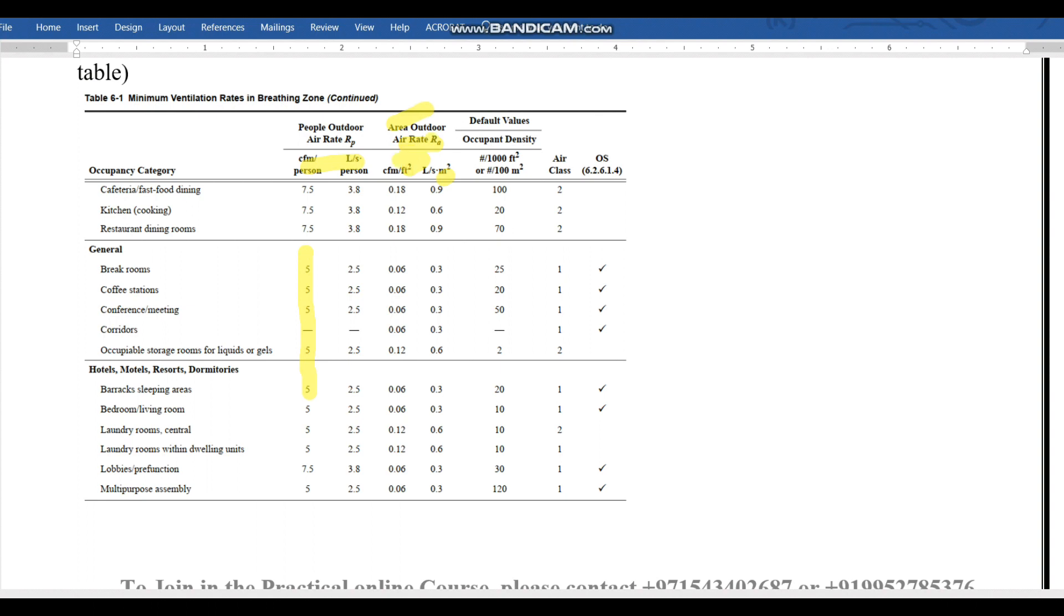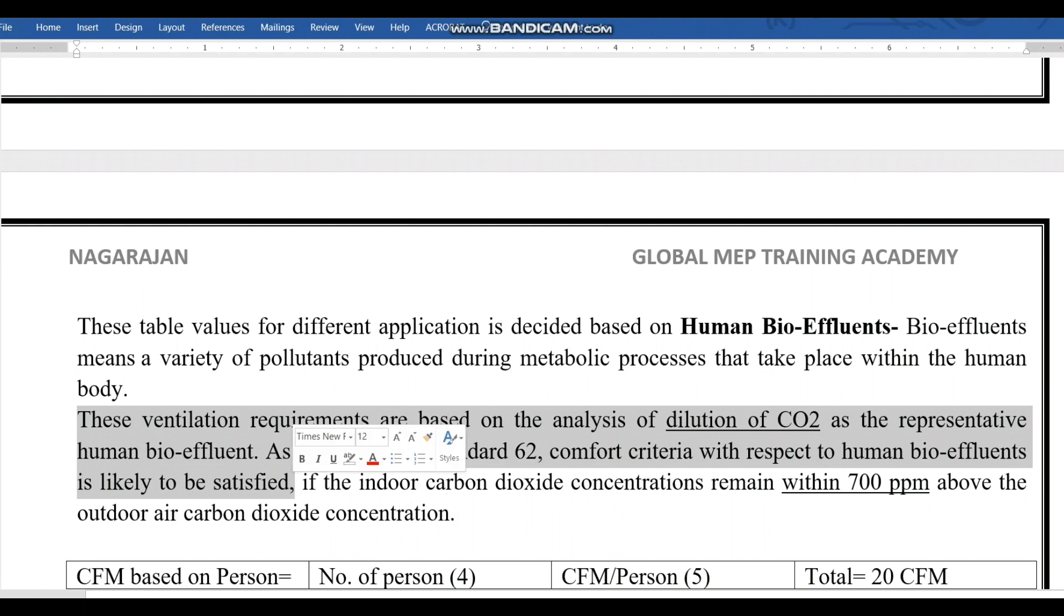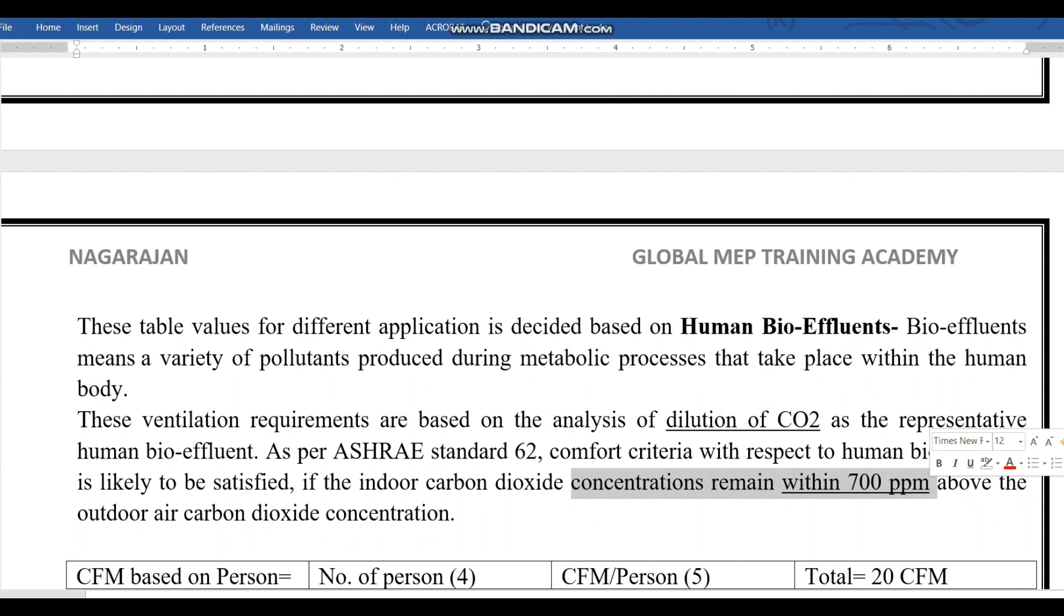This table is based on human bio-effluents, meaning a variety of pollutants produced during the metabolic process in the human body. We need to control CO2 to a particular limit. These ventilation requirements are based on analysis of dilution of CO2 as the representative human bio-effluent. As per ASHRAE Standard 62, comfort criteria with respect to human bio-effluents is likely to be satisfied if indoor carbon dioxide concentration remains within 700 ppm.